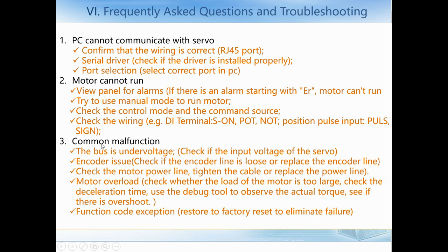Here are some common malfunctions. For bus under-voltage, check if the input voltage of the servo is correct. For encoder issues, check the encoder cable and sometimes replace it. For motor power line issues, tighten or replace the power line if it is loose. For motor overload, check whether the load is too large, check the deceleration time, and use the debug tool to observe the actual torque and see if it overshoots. For function code exceptions, restore to factory settings to eliminate the failure.